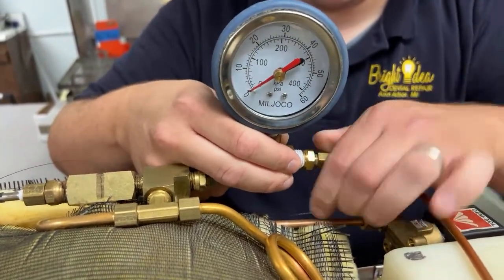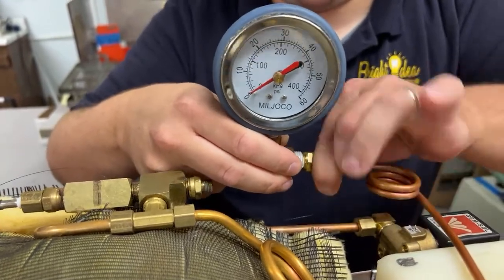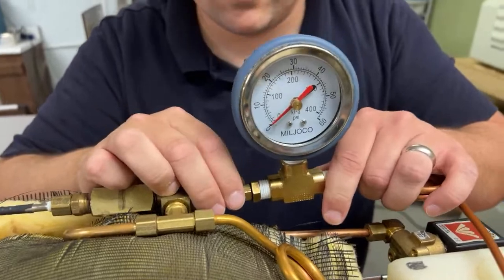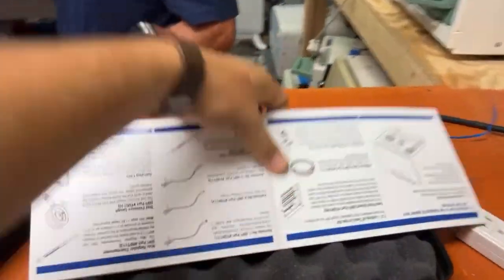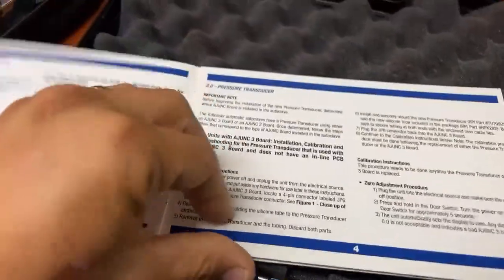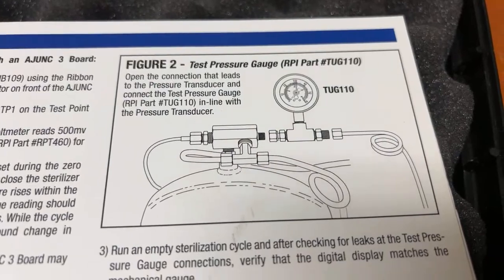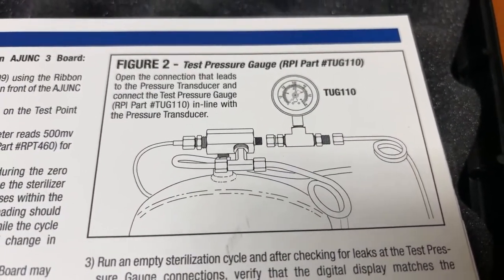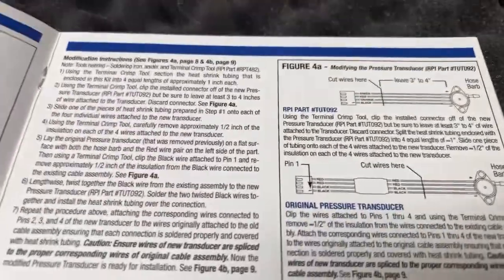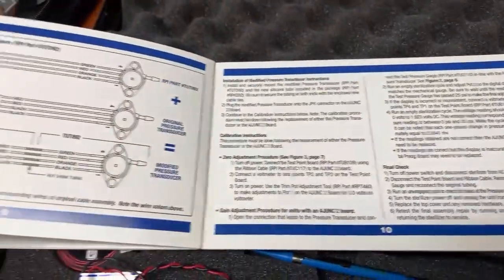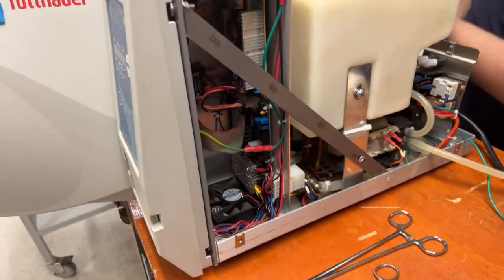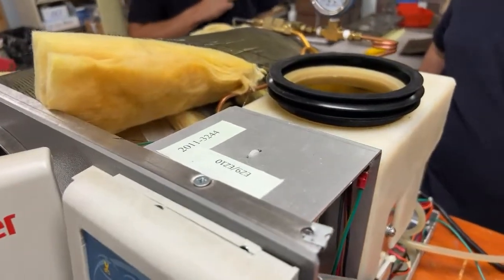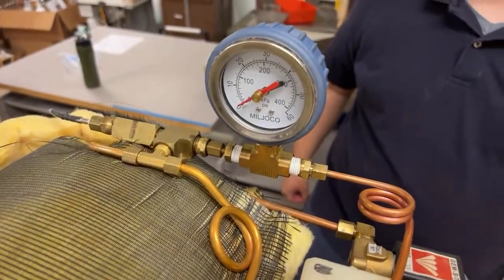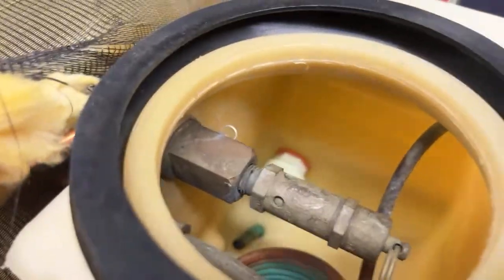This gauge was actually pointed the other direction, I think, and I had spun it around. So it's good to be able to reference the gauge as you're working on the unit. I'll show you right quick what we're doing. That is where the test pressure gauge gets put in. I'm trying not to make this super hard. The point of this training is really just to explore the basics of what this calibration looks like. So the gauge is now installed and that is looking good. The unit does have water in it, and we are ready to go.